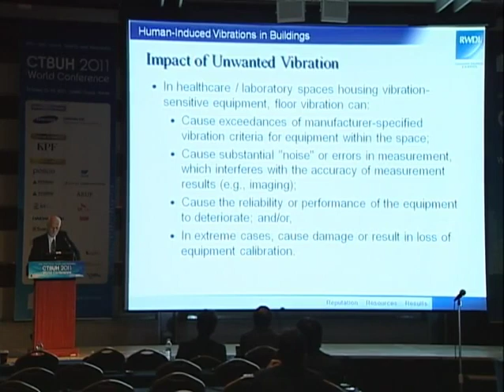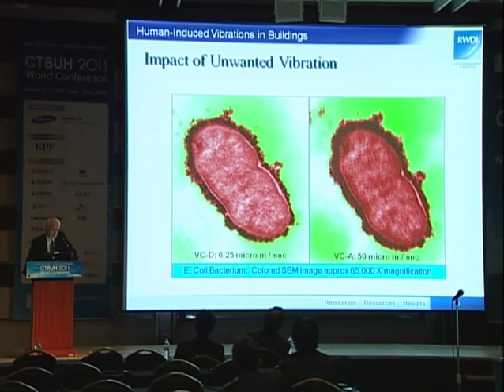Here's an example of an electron microscope image. On the left, we have a limit of 6 1/4 micrometers per second velocity on the vibrations, and the image is at 65,000 times magnification, and it's an E. coli bacterium. The image on the right has about 8 times that level of vibration, 50 micrometers per second, and if you look carefully you can see distinct degradation of the image, of the resolution. So this is just one example of the impact of unwanted vibration.